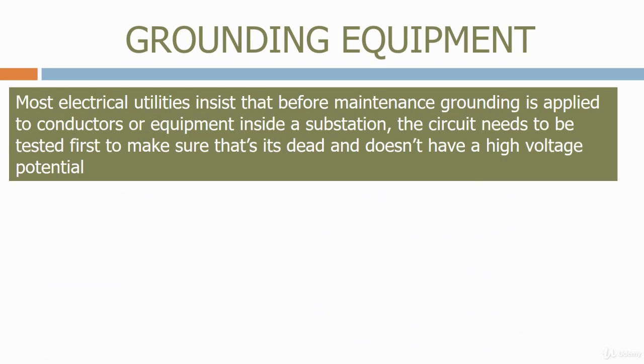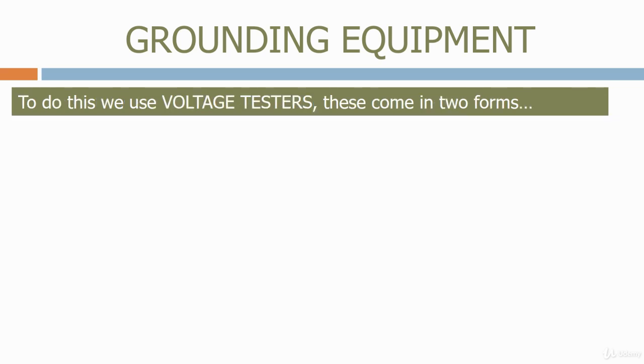Most electrical utilities insist that before maintenance grounding is applied to conductors or equipment inside a substation, the circuit needs to be tested first to make sure that it's dead and doesn't have a high voltage potential. To do this, we use voltage testers. These come in two forms.